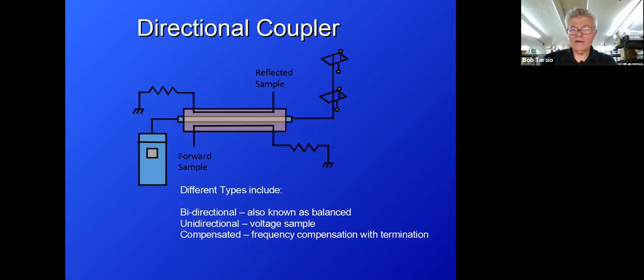Well, you notice that these couplers are schematically shown as dual port. We use 1 port for the meter, and then the same directional coupler can have a 2nd port, and that's an option that we sell actually, so that you can have a measurement port, which is also a balanced coupler on the other side. So you can have an identical set of ports, and you don't have to have 2 directional couplers to do that. You can do all of that in one line section. As a matter of fact, we can supply up to 3 additional ports. So you essentially have a 4-port coupler, but we use 1 for the power meter. So we supply those a lot to television stations and combiner systems where they want to look at things at different frequencies and whatnot, and everybody wants to have their own port to do that.